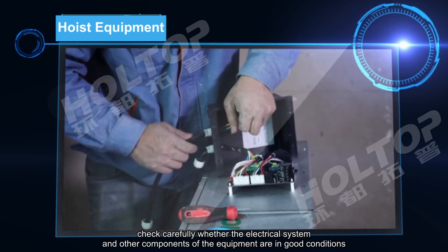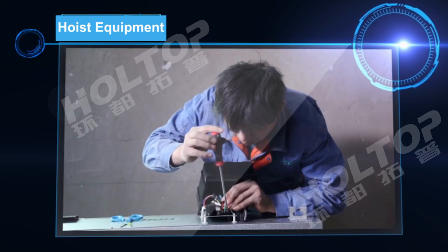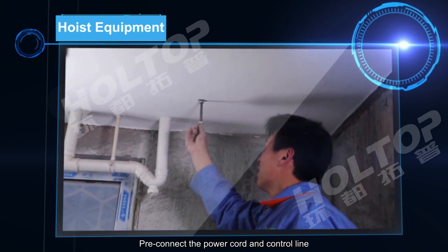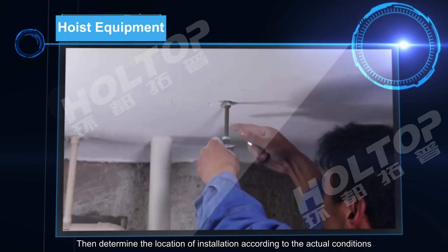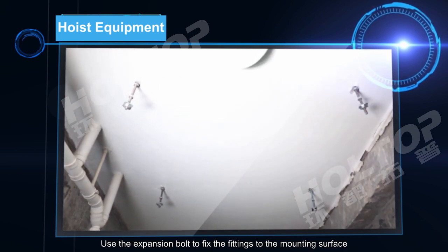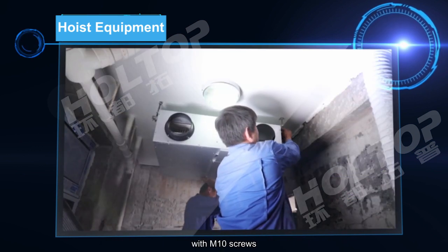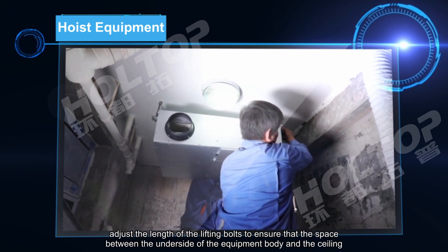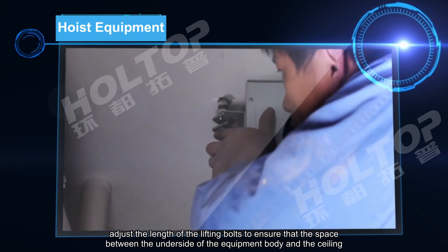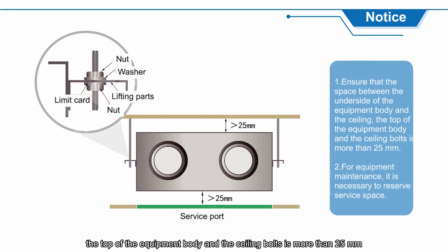Before installing the equipment, carefully check whether the electrical system and other components are in good condition. Preconnect the power cord and control line, and determine the installation location according to actual conditions, including power connection, demand lines, and layout. Use expansion bolts to fix the fittings to the mounting surface with M10 screws. After the equipment is hoisted, adjust the length of the lifting bolts to ensure the space between the underside of the equipment body and the ceiling, and between the top of the equipment body and the ceiling bolts, is more than 25 mm. Also ensure the equipment body is level.